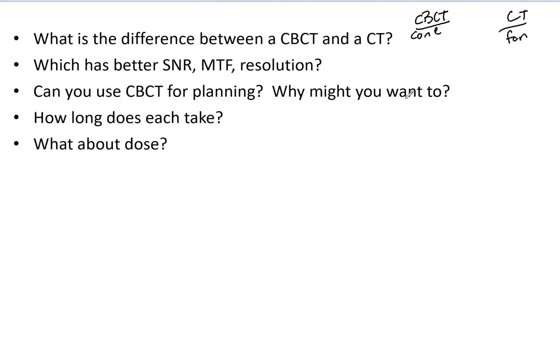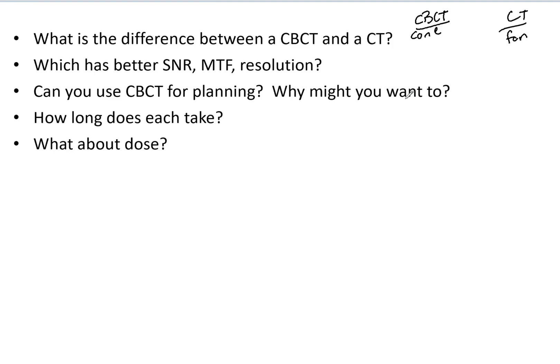This is a loaded question because you need a CT-number-to-electron-density calibration curve. You have one for your CT, but for your cone beam CT you need to ensure you have one specifically for it. At my clinic we only use cone beam CTs in emergency cases — if we want to change a plan, we take the patient back to the CT and redo the entire process rather than doing a quick scan with minor changes.